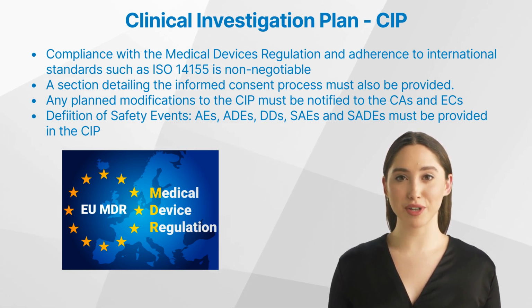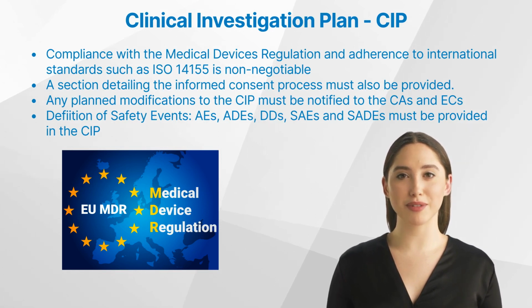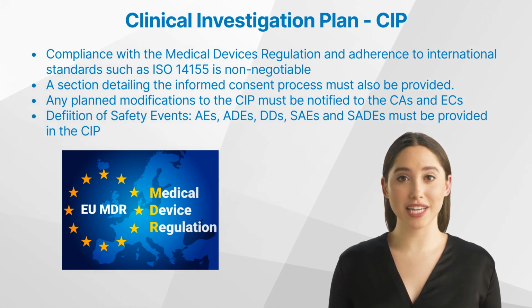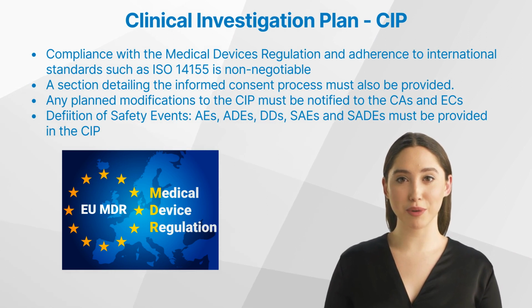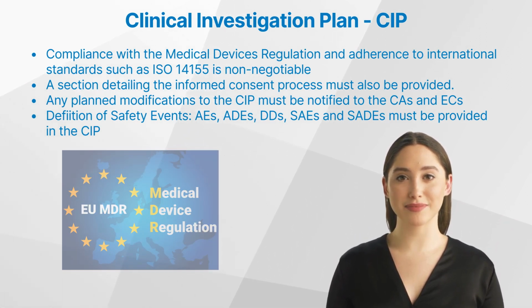Now let us have a look at safety events. A definition of the different types of safety events: adverse events, adverse device effects, device deficiencies, serious adverse events, and serious adverse device effects must be provided in the clinical investigation plan. A list of potentially expected safety events, as well as the plan for managing, reporting, and mitigating these events, should be described.